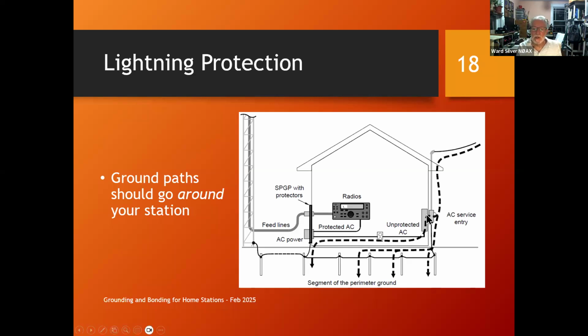So here's the unprotected AC line, and you ran that all the way over to your entry level single point ground panel, and you've got a surge protector on it. So the lightning, even if it gets all the way over here, has another very attractive path outside to another ground electrode. Lightning current is no different than any other current. It wants to take the path of least resistance. So give it all these paths of least resistance outside your house.